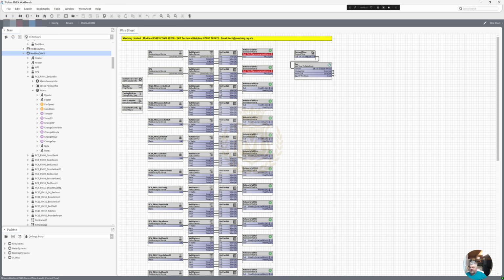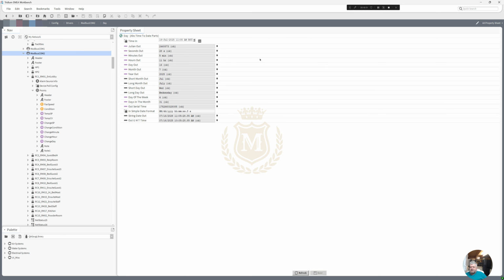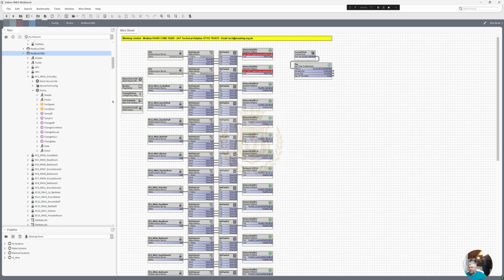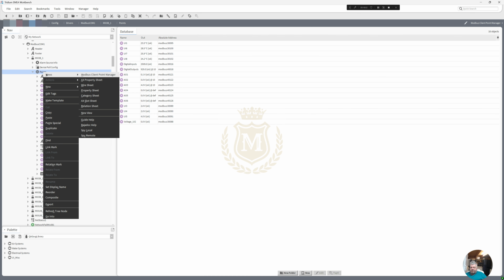And all we're doing there is taking the current time, and we're using a block that I never ever use anymore, which is, I'm trying to think what make it is now, but it was a block that you could buy, but I separate it differently now. I don't use this block. I don't use any third-party blocks now in many of my logic. I just use a Tridium standard logic. So that's that now. And of course we've got the mix units again with network faults if there's any faults. And these are Modbus. Let's just have a look at one of them. Views, wire sheet.